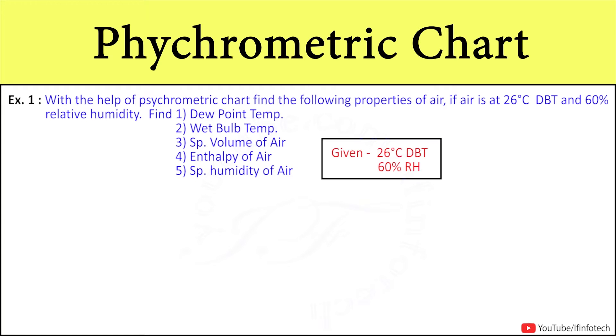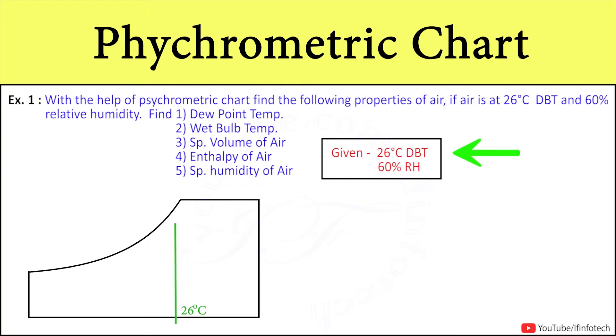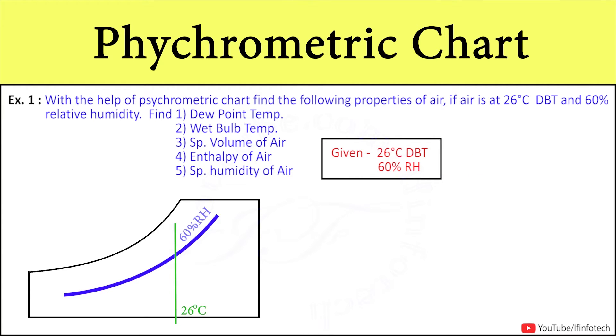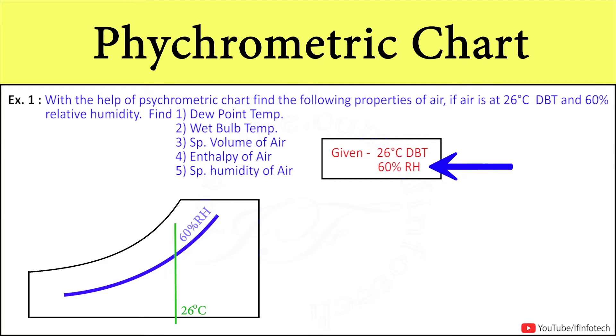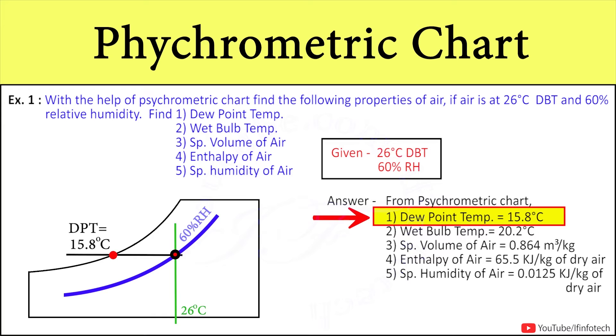The given data is air at 26°C dry bulb temperature and 60% relative humidity. On the psychrometry chart, we take the 26°C DBT line until it meets the curve at 60% relative humidity. Once plotted, we extend this line and get the dew point temperature as 15.8°C.